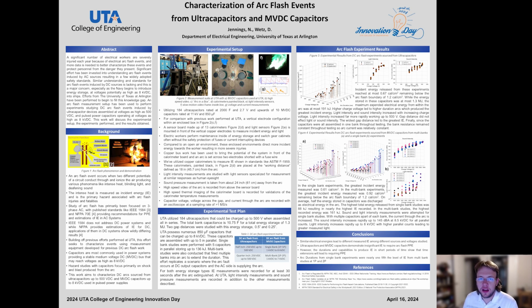Moving on to the arc flash experimental results, starting off with figure 3, we have our ultracapacitor measurements. Looking at the largest figure here, we see the arc duration compared against the charge voltage compared against the incident energy that's measured. The highest incident energy that we measured was 0.6 calories per centimeter squared, which falls below an arc flash boundary of 1.2 calories per centimeter squared. This arc flash boundary is established as the minimum distance, in terms of meters, that results in a second degree burn, and this second degree burn is characterized by 1.2 calories per centimeter squared.